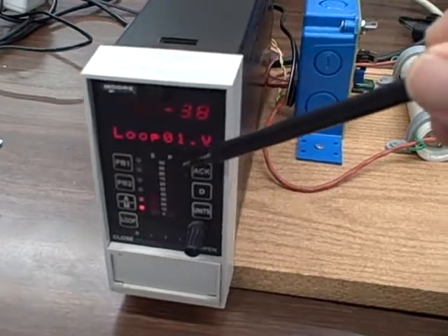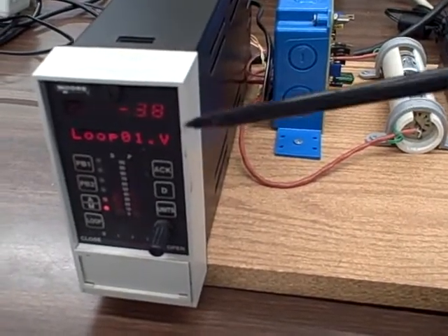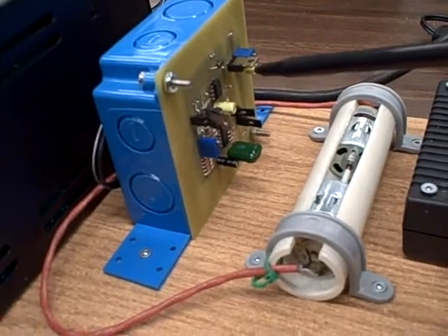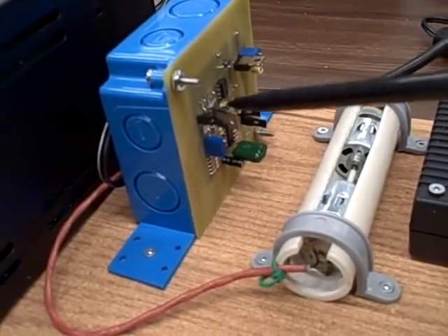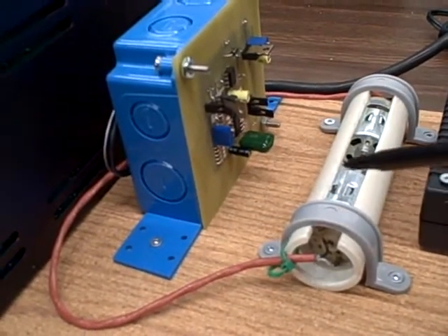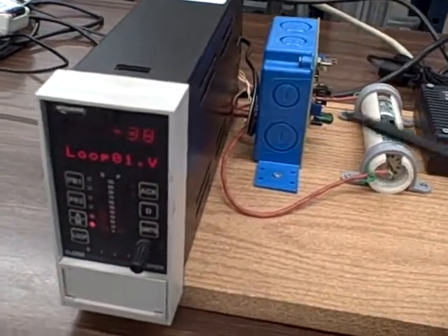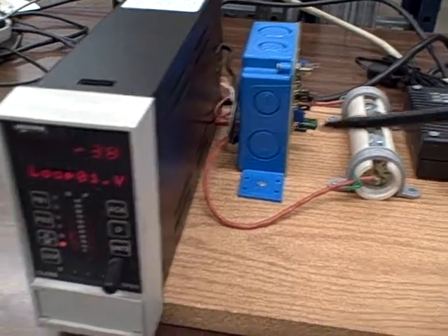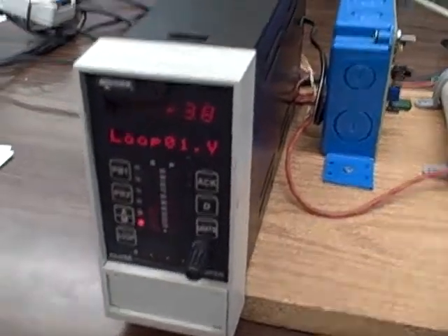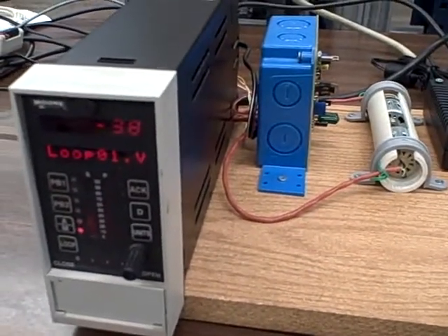speed of the motor. It's able to control the speed of the motor by sending a 4 to 20 milliamp output signal to a variable speed motor drive circuit, which sends a pulse width modulated power pulse to the motor driving at different speeds. So we have a self-contained control system here, a process which is the motor speed itself, and the controller here. We're going to demonstrate operation in automatic mode.